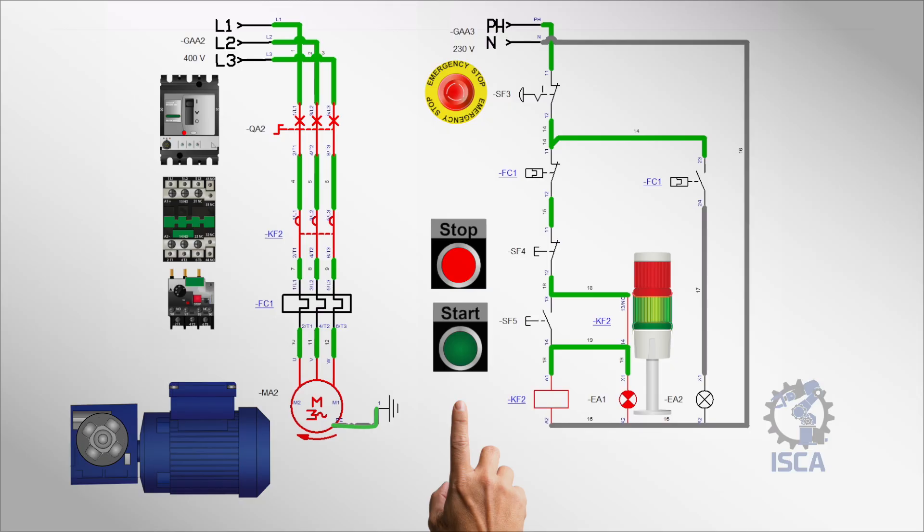The motor starts immediately at full voltage, hence direct online. The overload relay continuously monitors the motor current. If an overload occurs, the overload relay trips, opening the magnetic contactor and disconnecting the motor from the power supply.